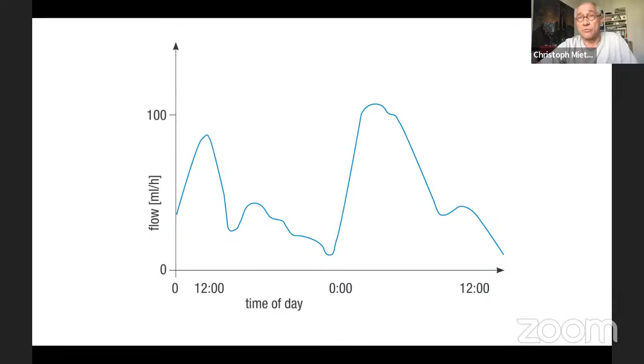And if you have a varying production rate, you should have a varying resorption or drainage rate. Then you should measure that, and then you would achieve reasonable drainage. But as we cannot measure that, we cannot systematically address flow regulation, and it might lead to both under or over drainage, and it's difficult to predict, even though it lowers the risk of over drainage for sure.